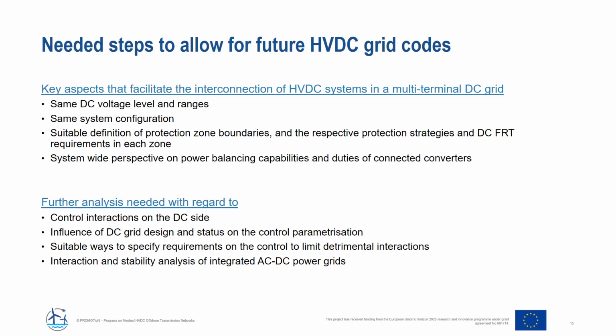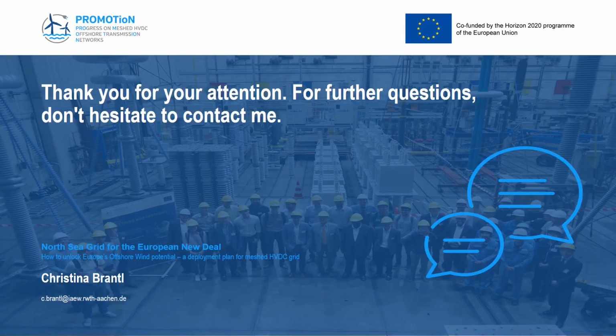And this is specifically a case for the DC side, but also for the AC side. So there's always a close interaction between the AC and DC side, especially under transient and contingencies. So there also needs to be an interaction and stability analysis of the integrated AC-DC power grids and their respective controls. So there are still a lot of challenges on the way towards HVDC grid codes.